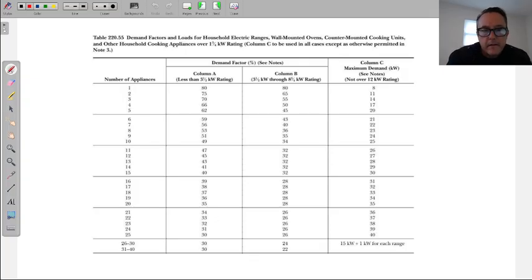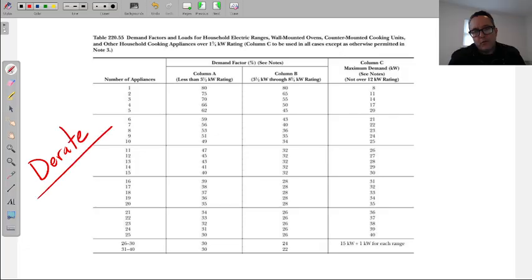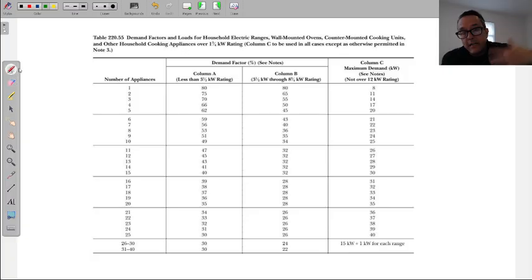Another way that we say that is to derate it. This is actually a word that is more used for conductors, when we go through the temperature correction factor and say, okay, the conductor's sitting at 175 degrees Fahrenheit, and the percentage that we're going to take is actually more derating. It's removing amperage from something, not factoring in any kind of time frame. But you will hear electricians mix it up and use that word a lot for demand factors. Derate, take away something from that.